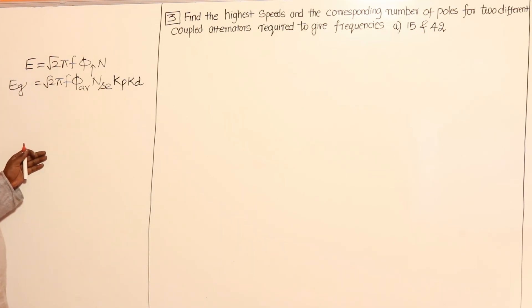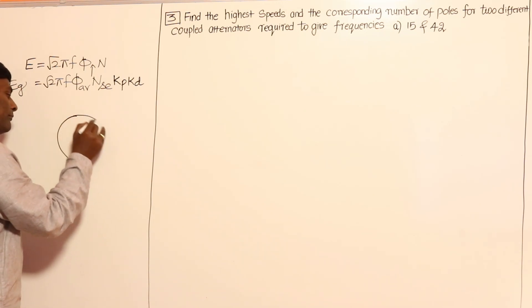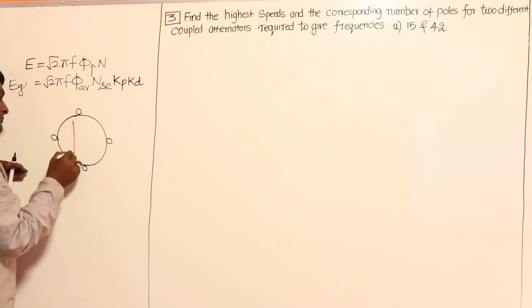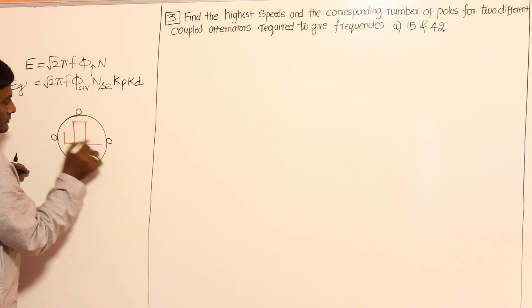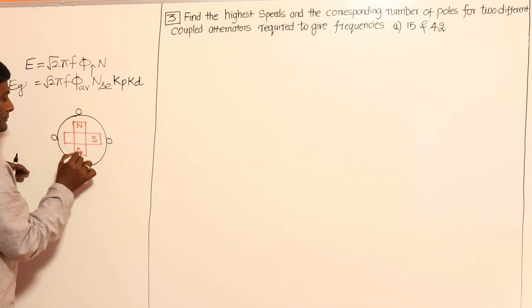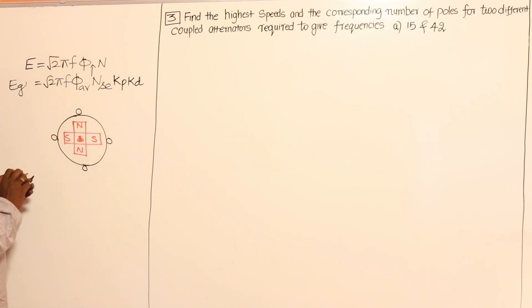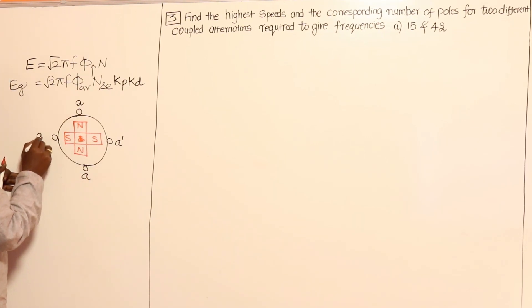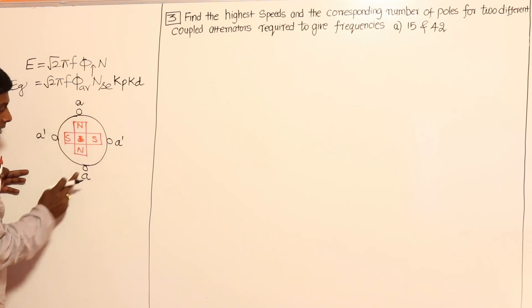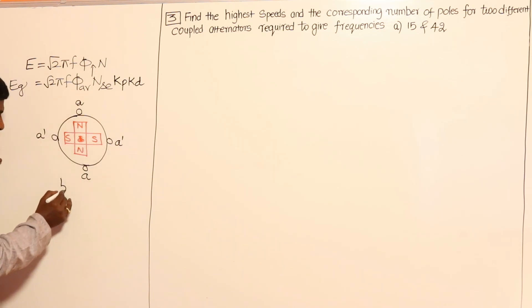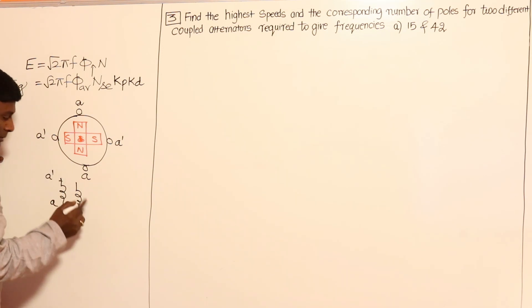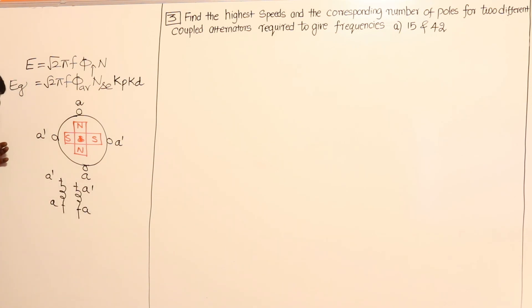Phi_average and N_se, where N_se is nothing but the series-connected number of turns. The induced voltage should be reduced because of short pitching angle, and again reduced because of distribution of the winding. So it will be multiplied by kp and kd — the winding factor. About N_se — for example, if I have a four-pole machine: under N-pole, if 'a' is there, under S-pole, 'a-dash' should be there for full-pitch coils. Under N-pole again 'a' will be there, under S-pole again 'a-dash' should come. So my induced voltage has two paths. For example, in the coil, voltage will be induced — here 'a', here 'a-dash' induced voltage.